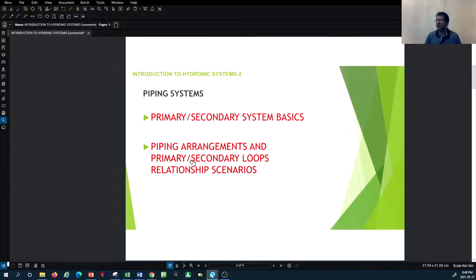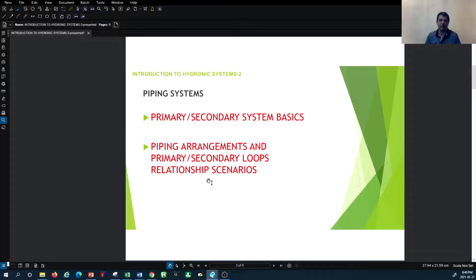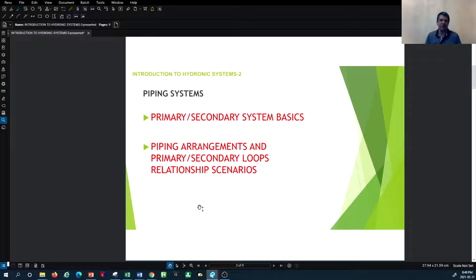Let's get started on today's tutorial. We are going to look at the piping arrangement on the primary-secondary hydronic loop. When we say hydronic loop, we are talking about a water system — this can be chilled water or hot water for a boiler system. It can also be applied to a glycol solution, which is very common in countries like Canada or the US where cold climates require protection of hydronic systems from freezing when recirculated outside heated buildings.